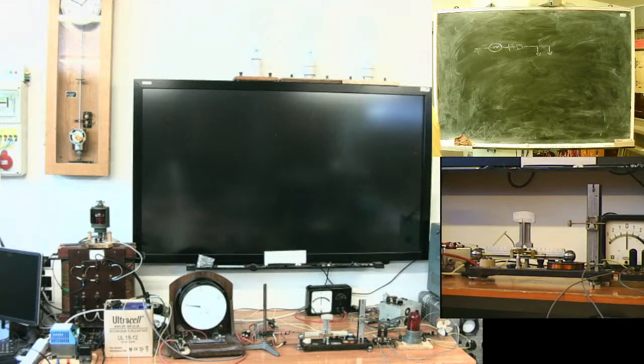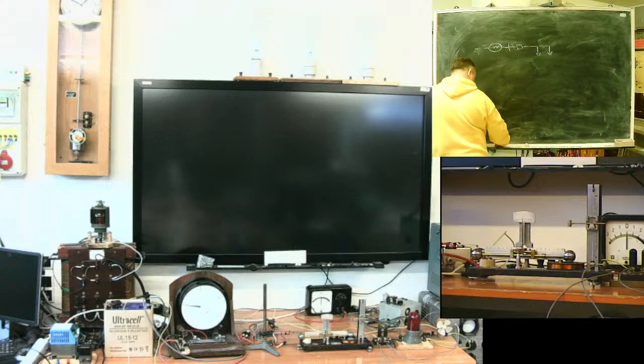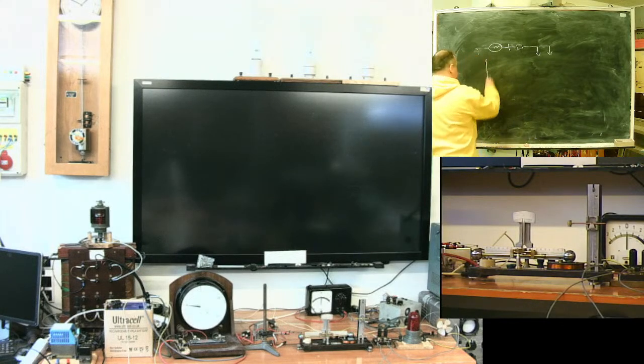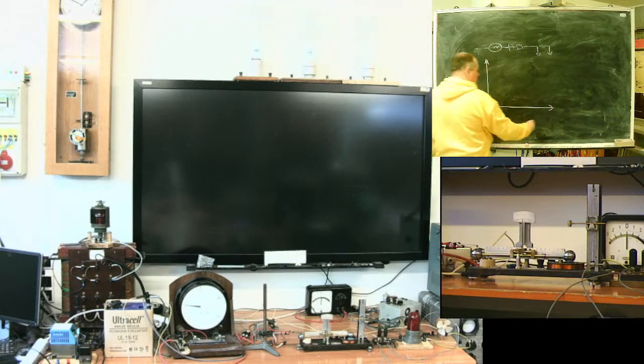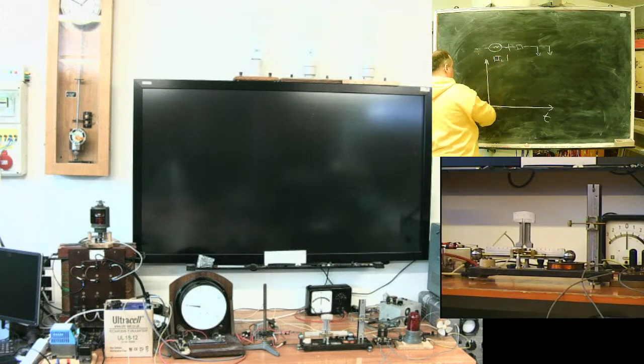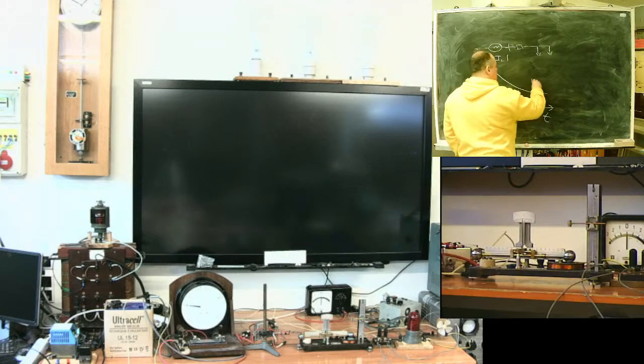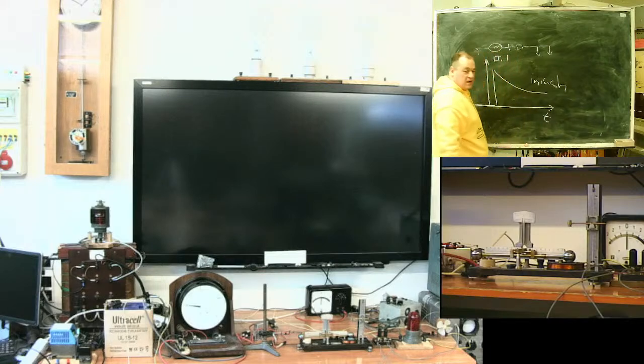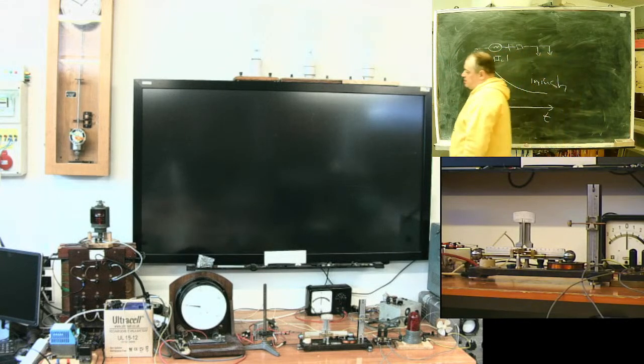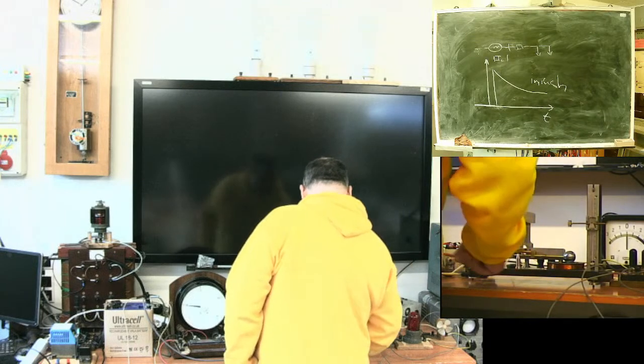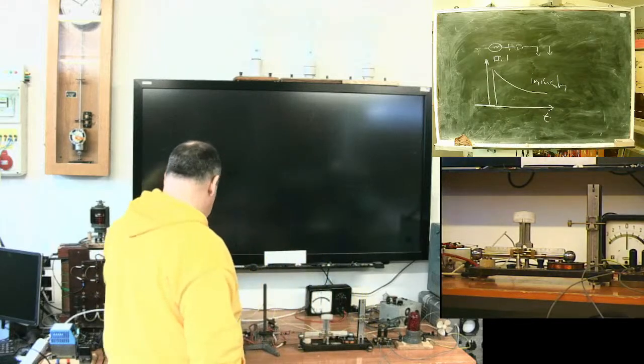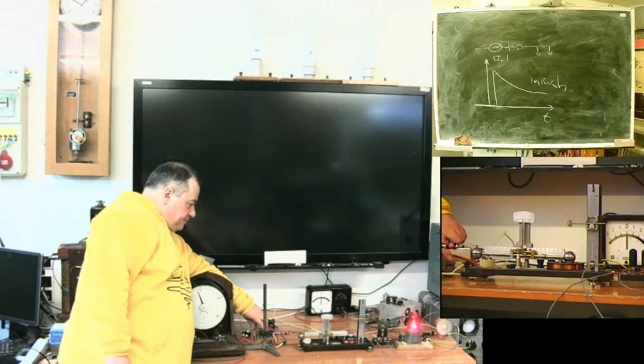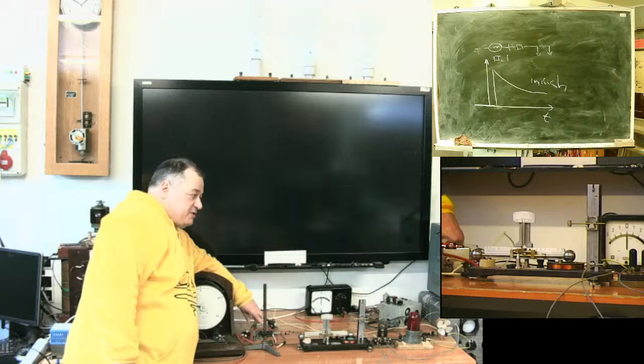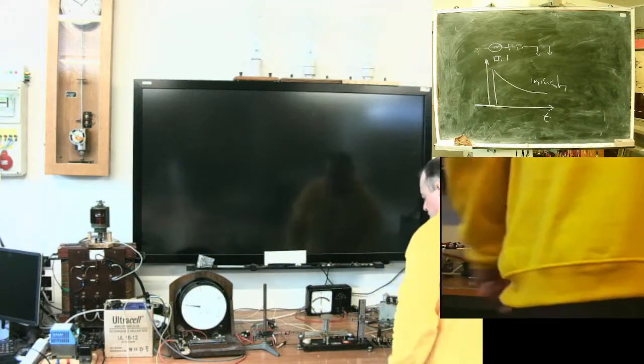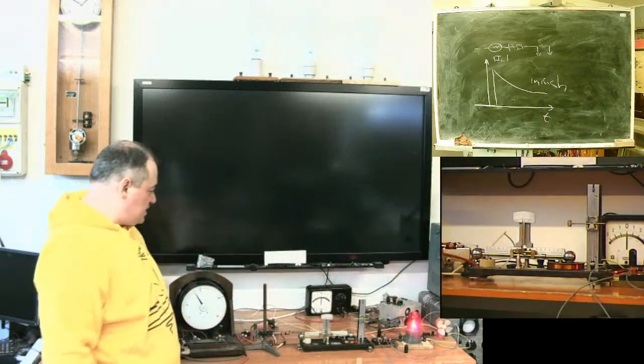For real loads, it's nothing special to see things like this. It's inrush or startup current. I deliberately made a wrong setup of protection. It trips on load inrush current at startup. In a case like this, see, I can switch.